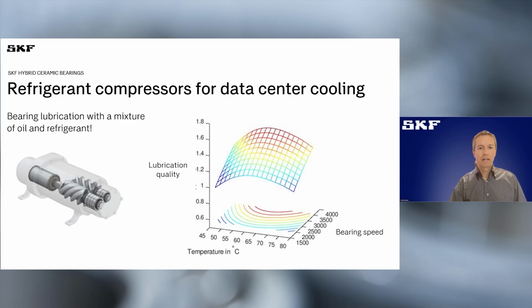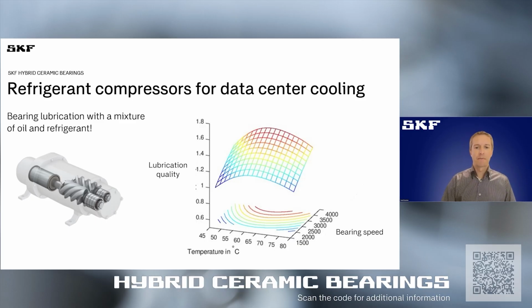Let me jump into one specific example where I have worked on quite extensively. This is an oil-injected screw compressor lubricated by a mixture of oil and refrigerant. Traditionally, these machines were used in air conditioning units like large chillers, but the same technology is also adopted in heat pumps or in the cooling for data centers.